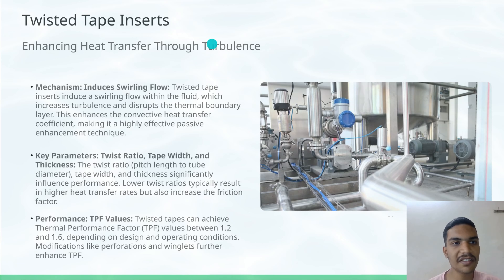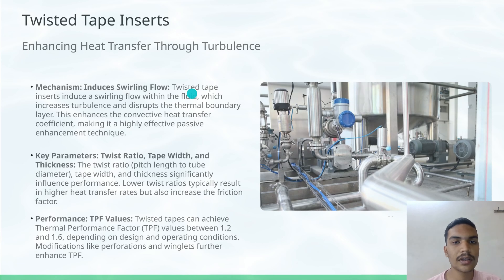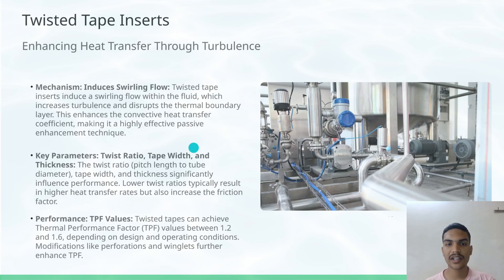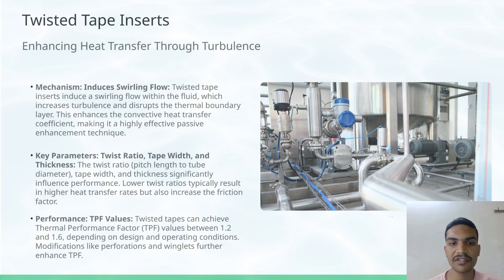The first technique is Twisted Tape Inserts. The twisted tape inserts induce a swirling flow within the fluid, which increases turbulence and disrupts the thermal boundary layer. Because of this, convective heat transfer is enhanced, and it is a very effective and most-researched technique in passive methods.